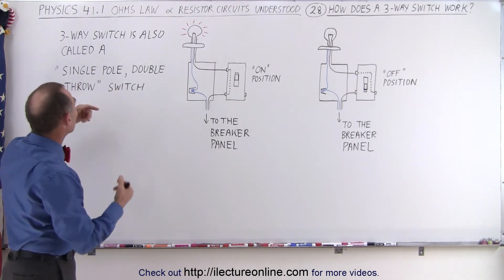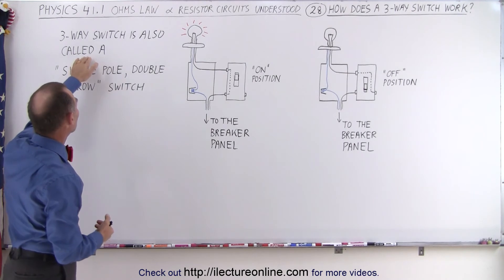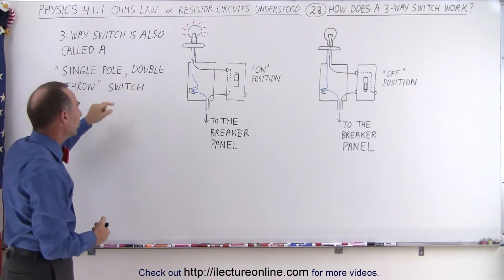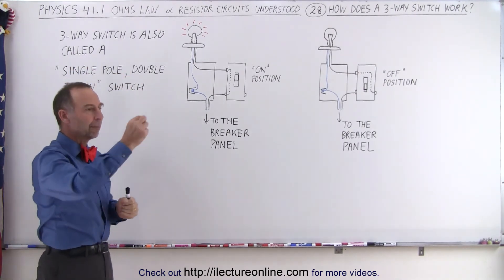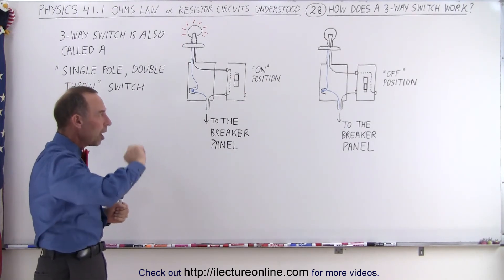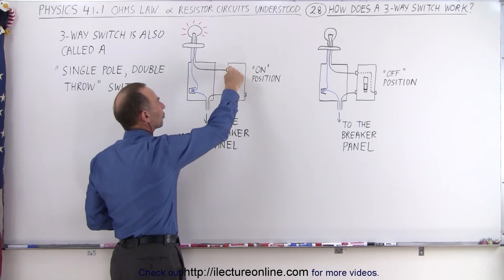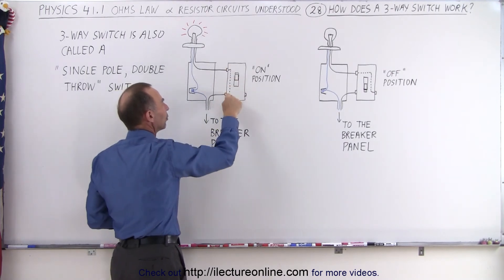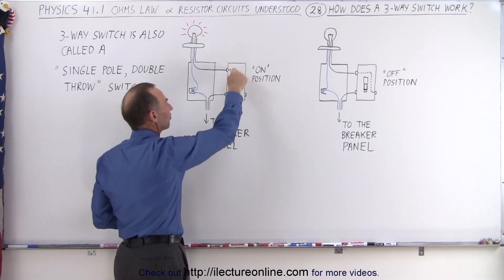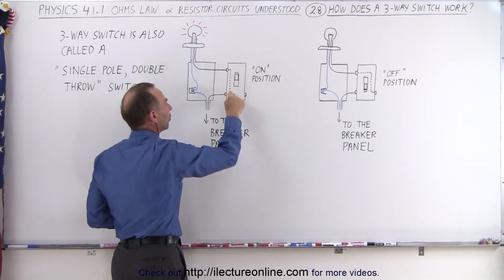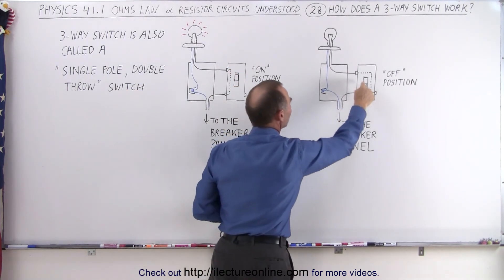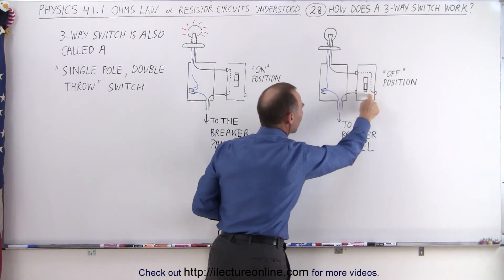But then also you need to realize that the three-way switch is also called a single pole double throw switch. In other words, by changing the lever in the on and in the off position, you can change where the connection goes from the top left, either to the bottom left, or from the top left to the bottom right. So the on position is top left to bottom left, and the off position is top left to bottom right.